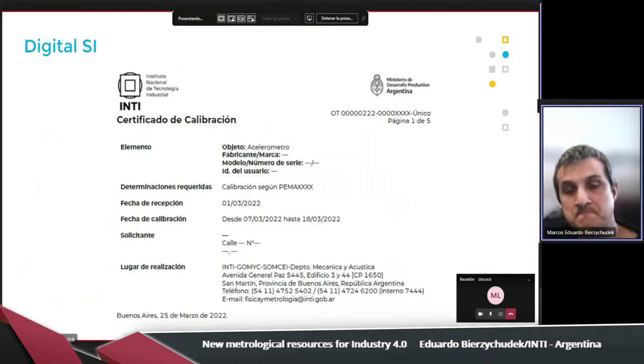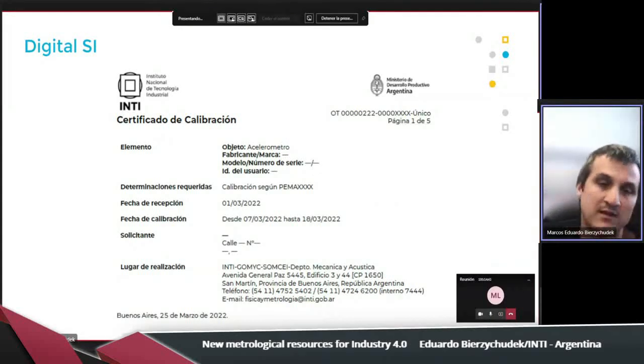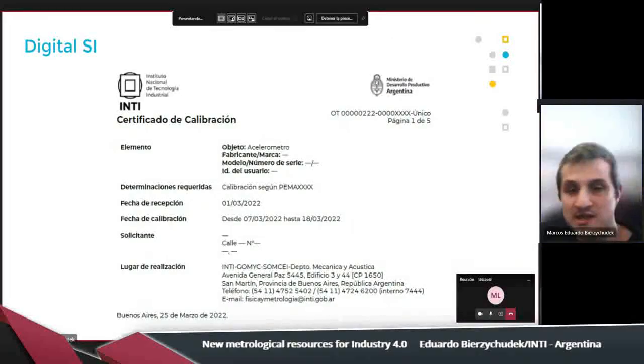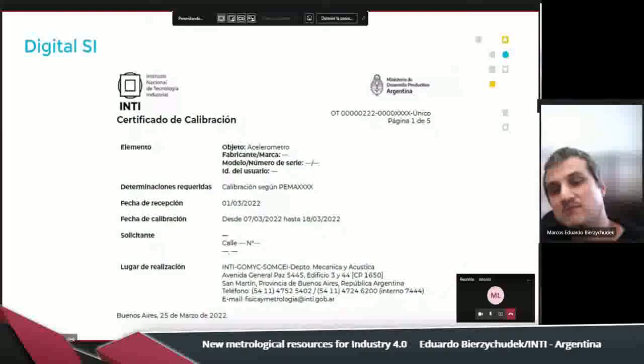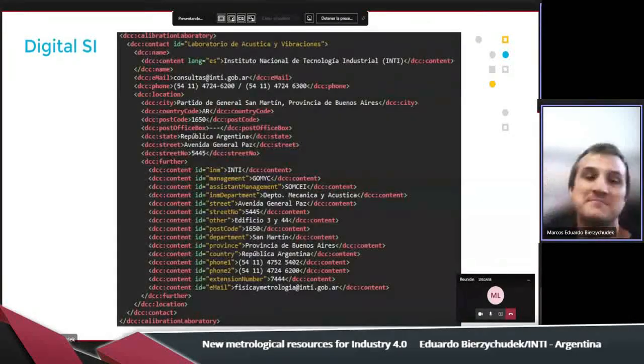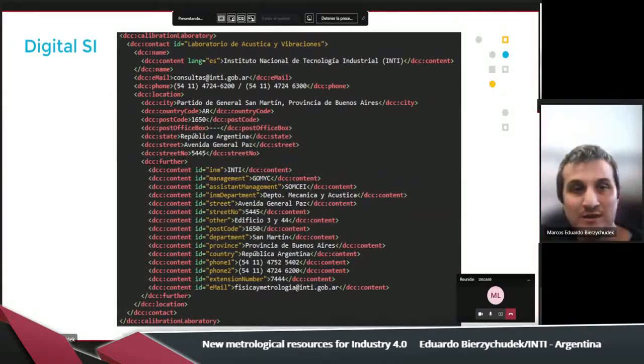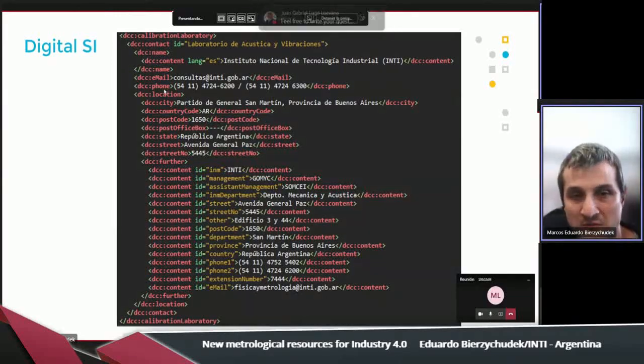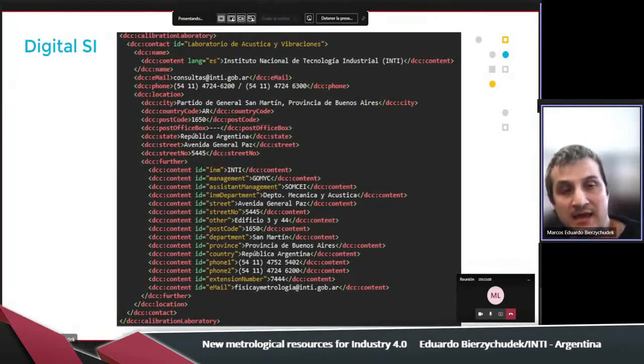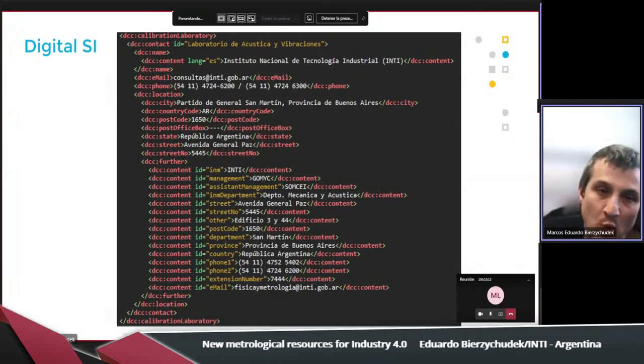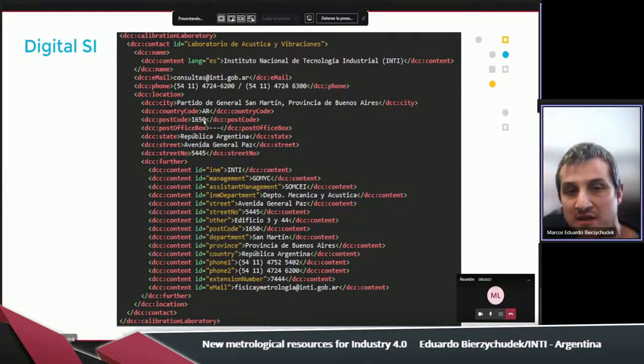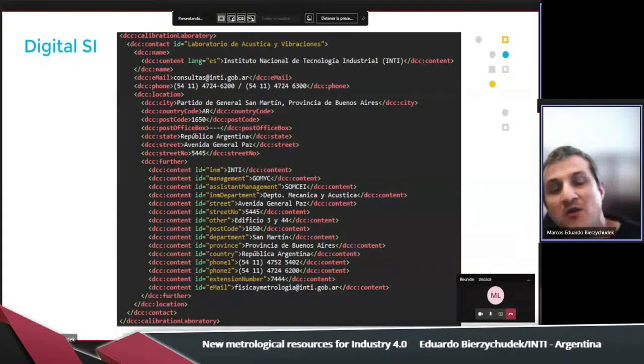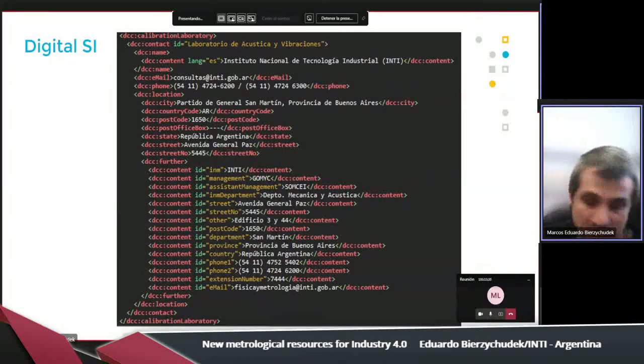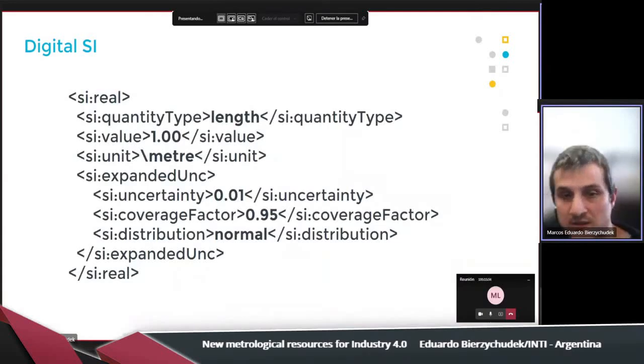For example, this is the first page of an actual certificate generated by INTI, where we have all the information about the device under calibration, the dates, the client, and also about INTI. So how do we change this information to the PTB format or the XML file? Just in this way. Each of these levels indicates some information. That level is defined by the PTB format. So, for example, postcode means the postcode of INTI in this case, and here we have the information in the middle of the two levels. This is a typical XML file, but the names of the levels are indicated by the PTB format.